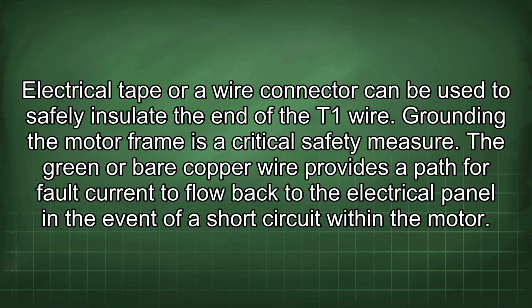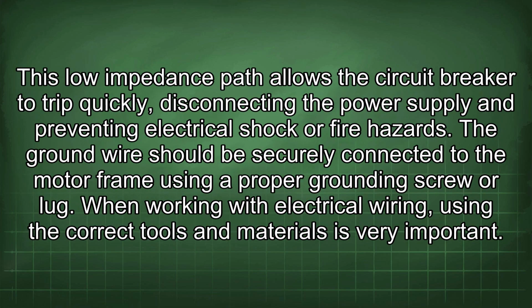Grounding the motor frame is a critical safety measure. The green or bare copper wire provides a path for fault current to flow back to the electrical panel in the event of a short circuit within the motor. This low impedance path allows the circuit breaker to trip quickly, disconnecting the power supply and preventing electrical shock or fire hazards. The ground wire should be securely connected to the motor frame using a proper grounding screw or lug.